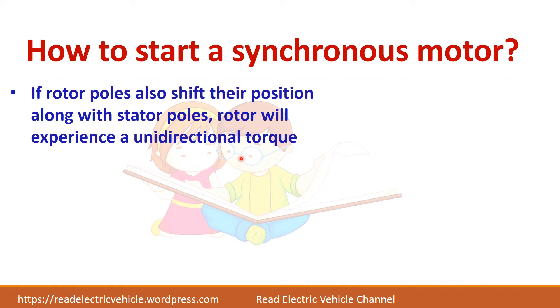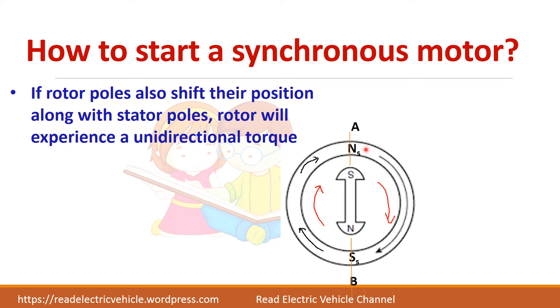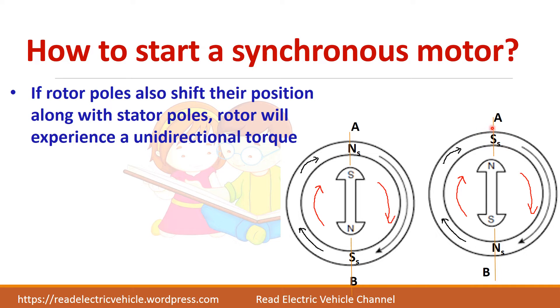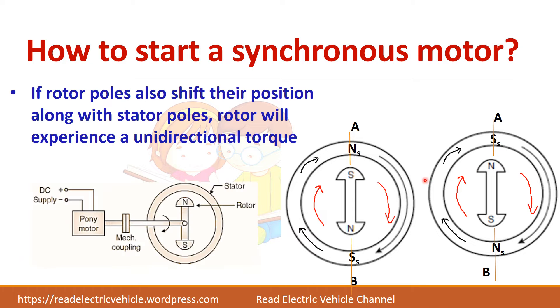Then how to start a synchronous motor? We have seen that the stator poles change their position every half cycle. If the rotor also changes its position according to the stator, the rotor will experience a unidirectional torque. In the first half cycle the north pole of the stator and south pole of the rotor are magnetically locked. In the next half cycle when the stator changes to south pole, the rotor should also rotate along with the stator so that the north pole of the rotor and south pole of the stator get linked. This can be done by using an external prime mover to make the rotor rotate at the same speed as the stator so that locking occurs.